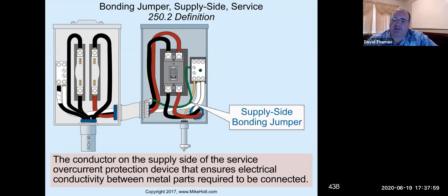The reason is that if anything gets induced into this conduit, we need to remove those electrons that are being carried back and forth in the wires. We have to bond this to dissipate some of those electrons, in addition to protecting and having conductivity from the wires coming from this side to this side. The neutral here does tie the neutral coming in from the service through the conduits back in here, but there is no assurance that the conduit is carrying any electrons that get induced into it, and that we have conductivity. So if any short circuits do occur, I'll show you in a second how this whole thing works.